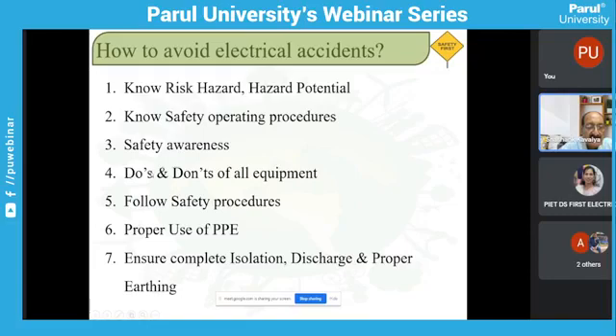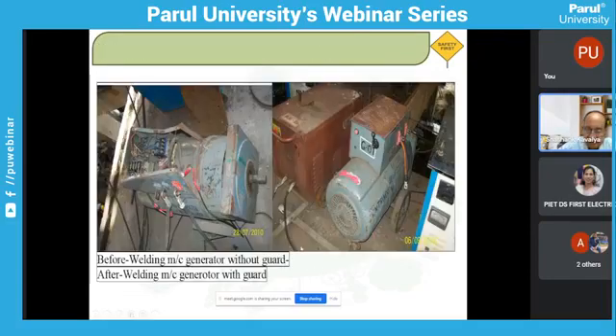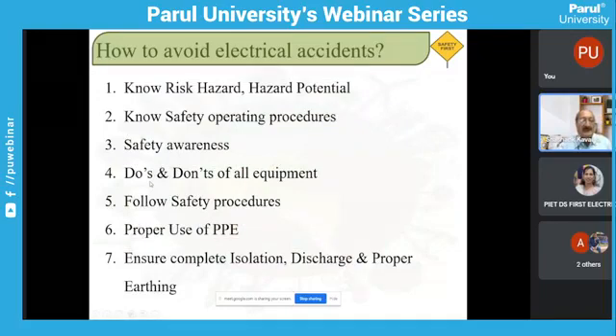Then most important is this: do's and don'ts. Everywhere there are do's and don'ts. If I want to insert my breaker and start supply, there is a system - I have to follow the safety operating procedure and know my interlocks. One should not bypass the interlocks. Bypass means making a direct connection. Without switch and fuse, if you make a direct connection, then without protection you will be in trouble.